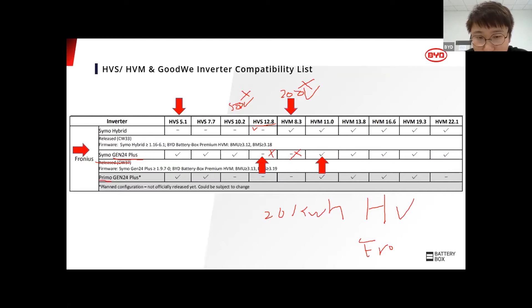So check carefully if the customer says, okay, I probably need a 12 or 15 kilowatt hour system, they can run the HVS. So for example, the customer needs a 20 kilowatt hour system and wants high voltage with the Fronius inverters. What can the customer do? They need to parallel more batteries. For example, the customer can get two HVS 10 kilowatt hour in parallel, or they can get one HVM, 20 kilowatt hours in one tower. So they give you a difference, but definitely this is more on the performance. This is more on the cheaper system, more affordable, and a larger system.